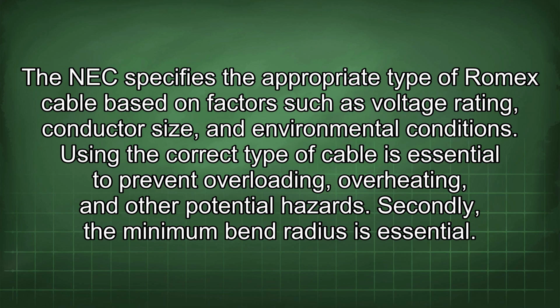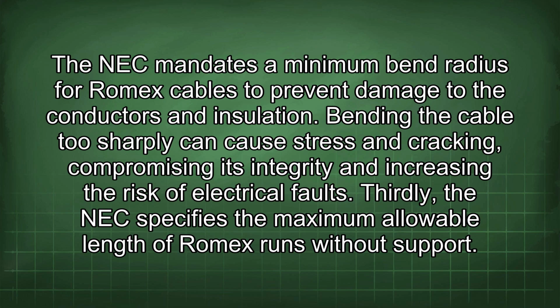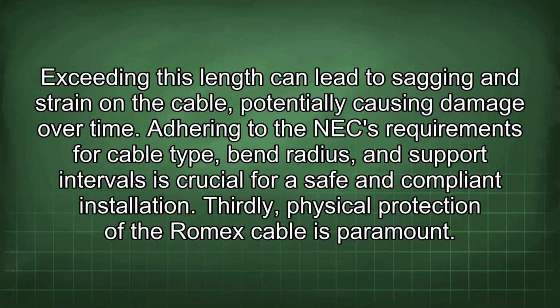Secondly, the minimum bend radius is essential. The NEC mandates a minimum bend radius for Romex cables to prevent damage to the conductors and insulation. Bending the cable too sharply can cause stress and cracking, compromising its integrity and increasing the risk of electrical faults. Thirdly, the NEC specifies the maximum allowable length of Romex runs without support. Exceeding this length can lead to sagging and strain on the cable, potentially causing damage over time.